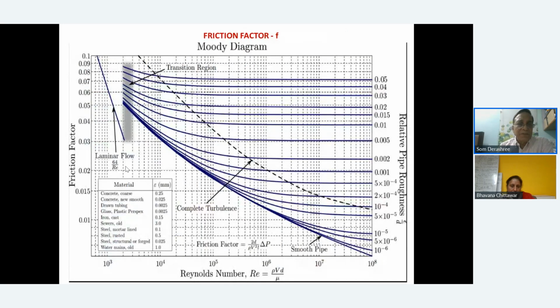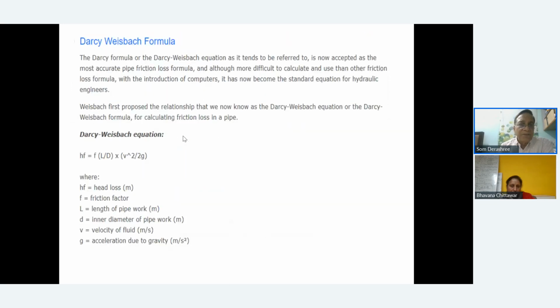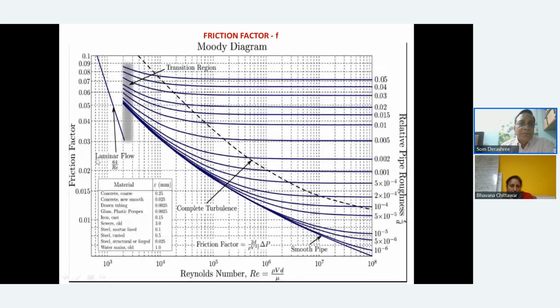And for the friction factor F in this formula, we have to find the F value. Now this F is from Moody's chart. Moody's chart is based on the Reynolds number, which we already know. We have to know the relative roughness factor, which is epsilon by D. Now epsilon is defined for different materials. These values are already defined here, for concrete, cast iron, steel, rusted steel, forged steel, or mains pipes, etc. So epsilon is known, and D is the diameter of the pipe, which is known. So you arrive at this roughness factor. You know the roughness, you know the Reynolds number, and the third is the complete turbulence zone. Knowing the roughness factor and this, you will arrive at this particular friction factor here.